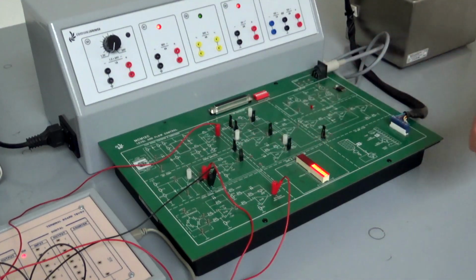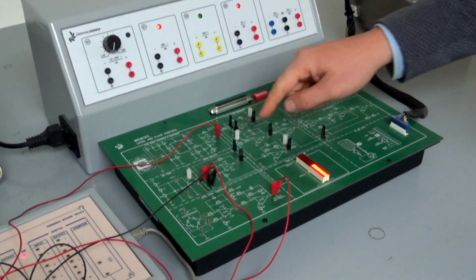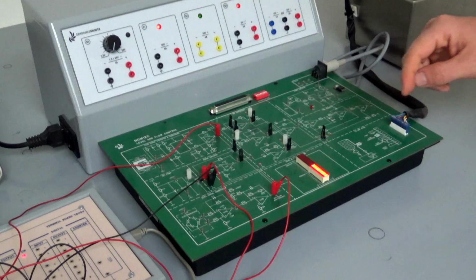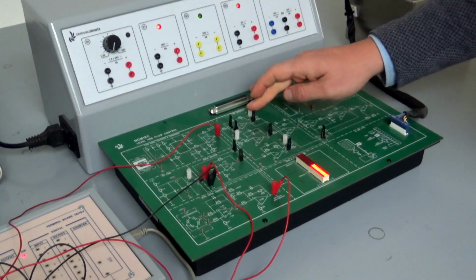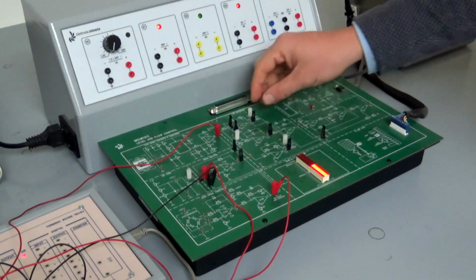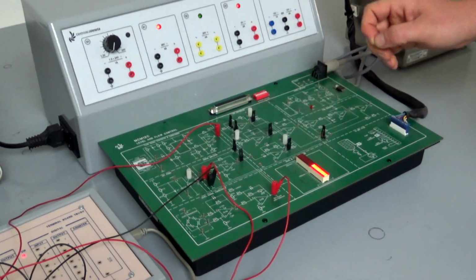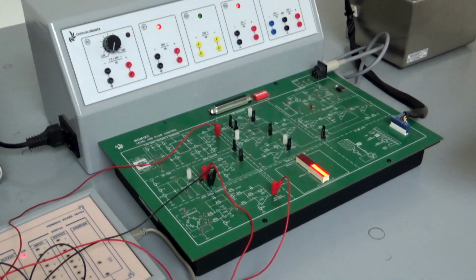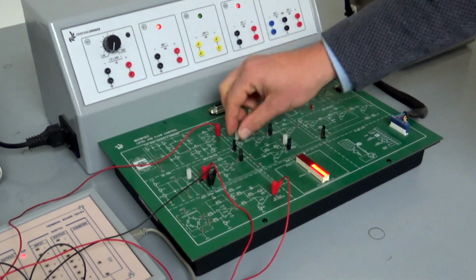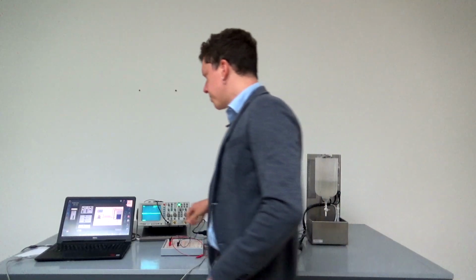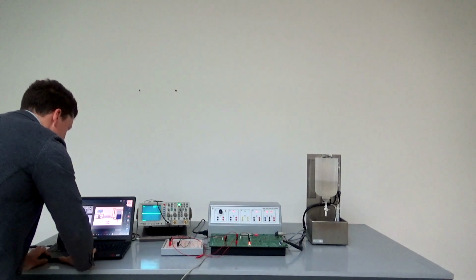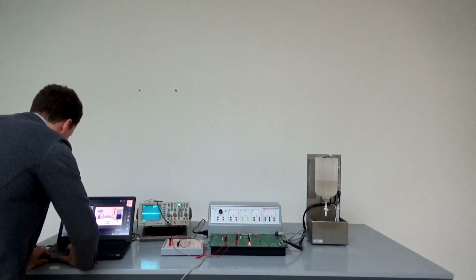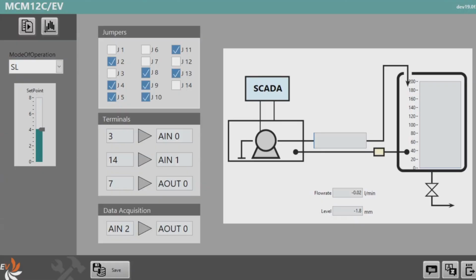In the central section of the main unit, we have 3 potentiometers concerning the 3 constants of the PID control. So you got the proportional part, the integrative and derivative part. So by acting on these potentiometers, I can regulate the dynamics of the PID process. So now going back to the PC, I can see the numerical indicators of my level and of my flow rate. So by acting on the set point here, I can see the system is responding fast enough for my process.